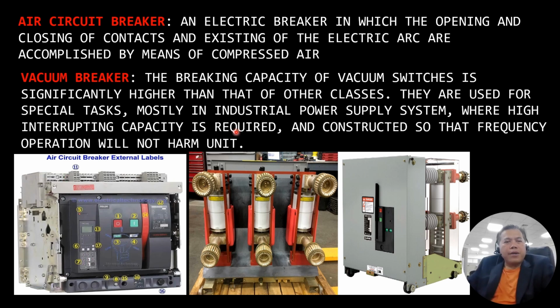So about the vacuum breaker. Vacuum breakers, guys, we always see in the utility. When I was in Saudi Arabia, we did the retrofitting of our 13.8 kV vacuum circuit breaker. Vacuum circuit breakers have a significantly higher switching capacity. They are used for special tasks, industrial power supply systems, or where high interrupting capacity is required. Frequent operation will not harm the unit. Right?